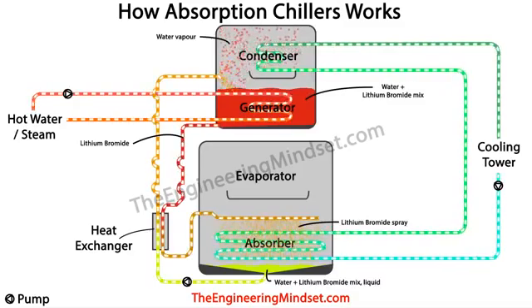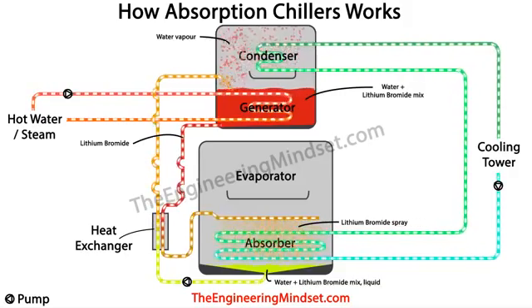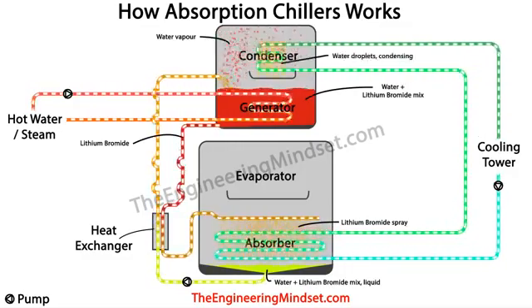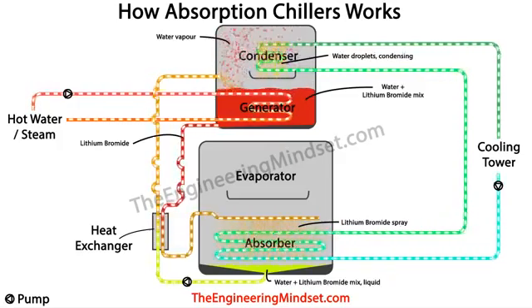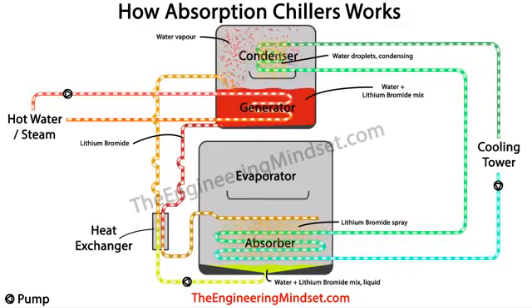Next, we want to condense the hot water vapor in the condenser to bring it back to a liquid. So we pass water in a sealed pipe through the condenser and circulate it around to the cooling tower where it will be able to reject all the heat that it collects. The temperature of the cooling tower water is enough to cause the hot water vapor to condense into a liquid as it comes into contact with the surface of the pipe, so it will rain down and collect in the collection tray just below, just here.